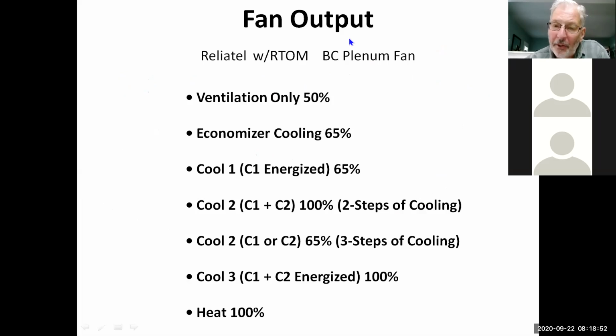And as we talked about earlier, when you're setting up airflow, remember we have some different airflows than we used to deal with in the past on these models. So ventilation is 50%, economize is 65. Cool 1 is going to be 65, cool 2 is 100, cool 3 is 100, and heat is always 100%. Because of UL and AGA regulations, anytime we're in heat stage, first stage or second stage, we're going to have 100% airflow in these units.